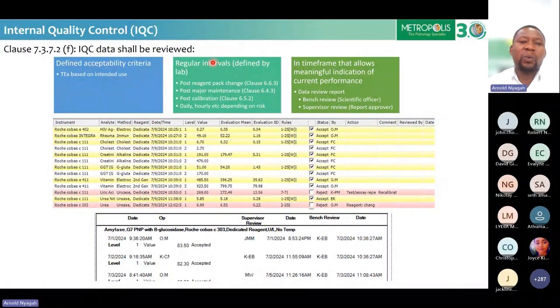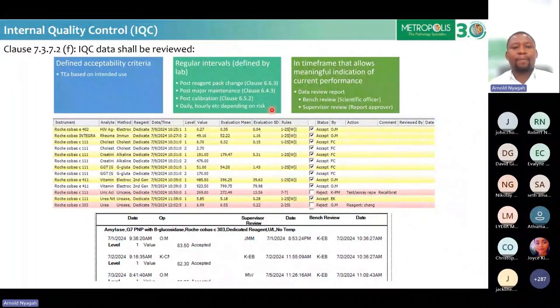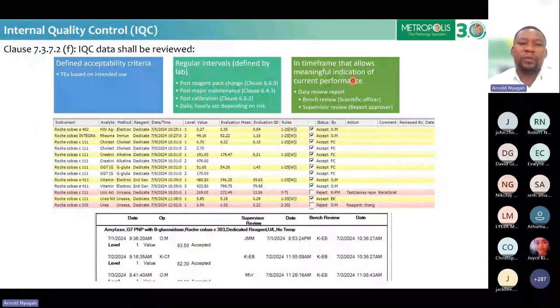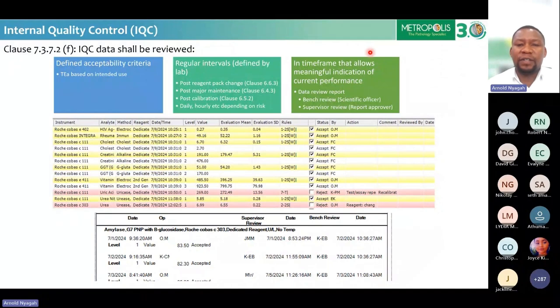Then also we have regular intervals. We have some recommendations in our procedures, and the standard also recommends some instances where you need to review, especially post reagent pack change, post major maintenance, and post calibration. The other ones you can define according to the risk of that test to the patient. Then in a time frame, once you define the time frame for review, you can generate various reports.